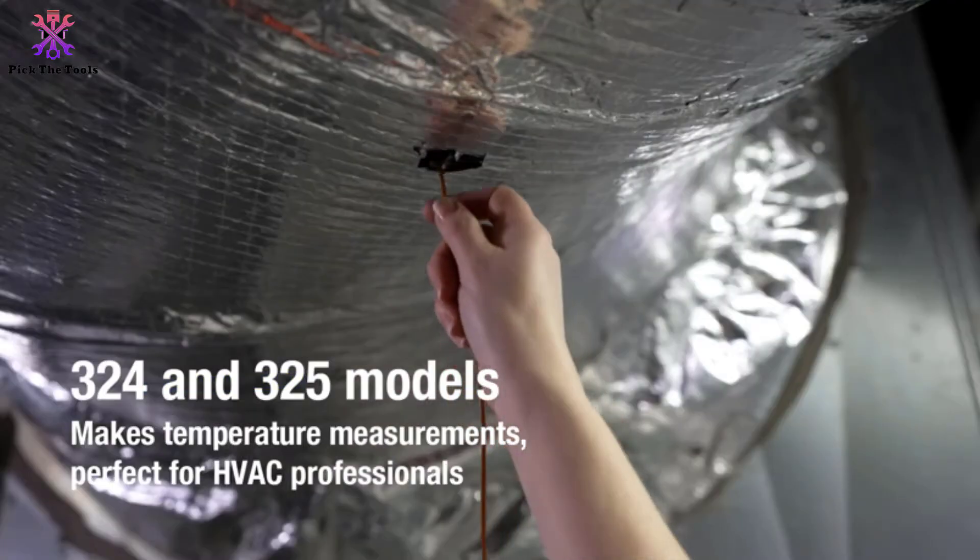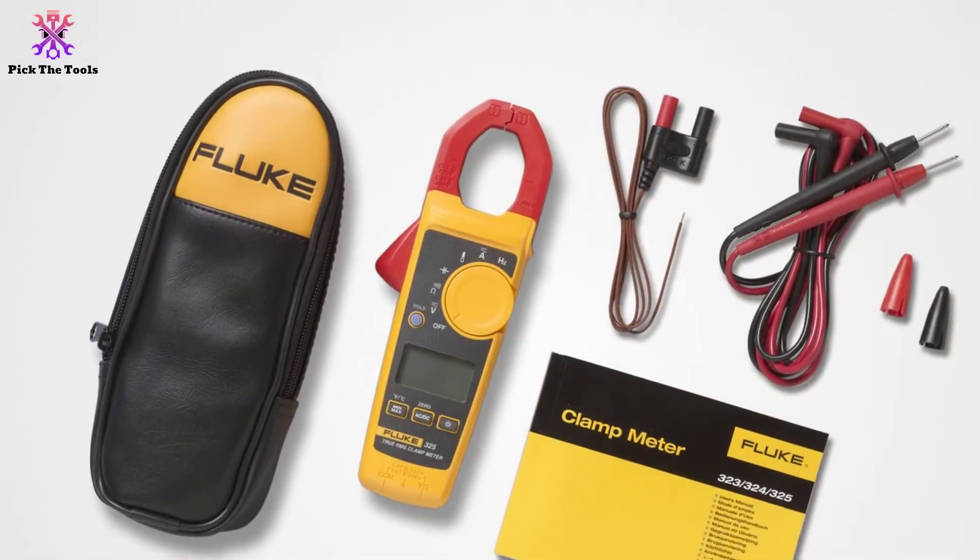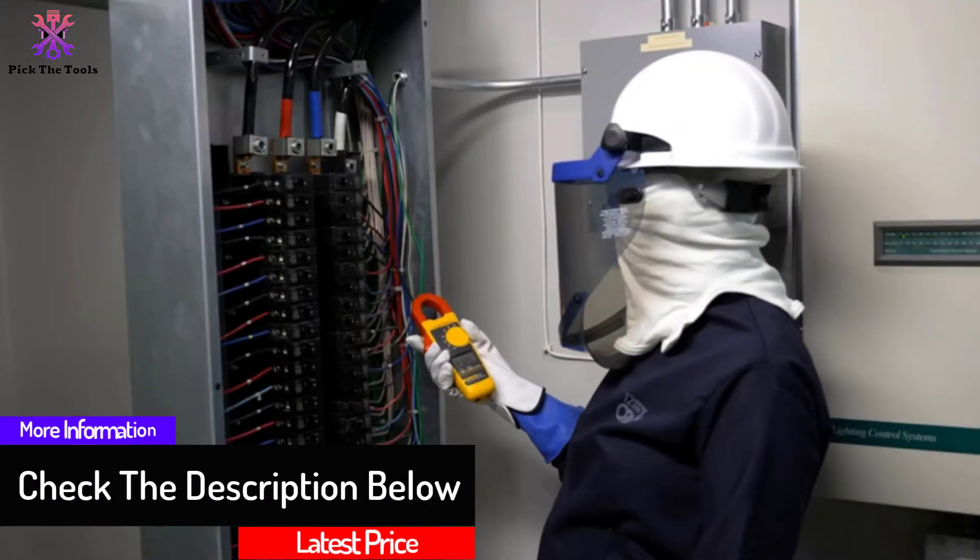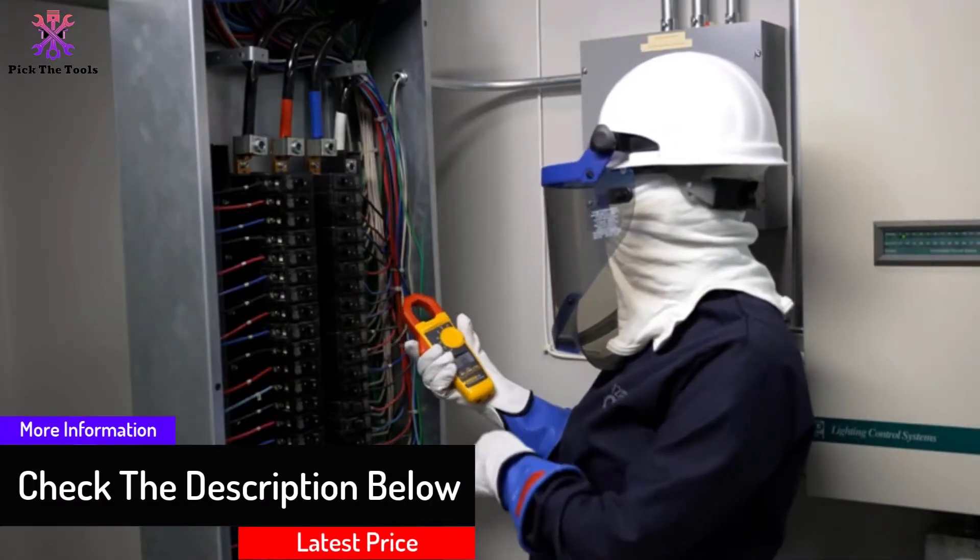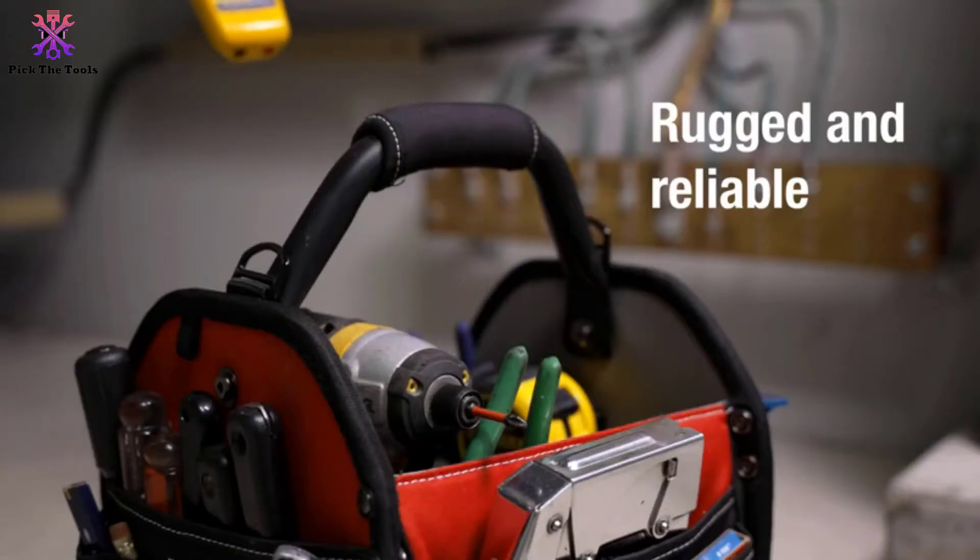This small and portable meter can measure AC and DC amperes, AC measure up to 400 amps, and AC and DC voltage to 600V. It is also suitable for working on category IV installations of up to 300 volts, and category 3 installations up to 600 volts.